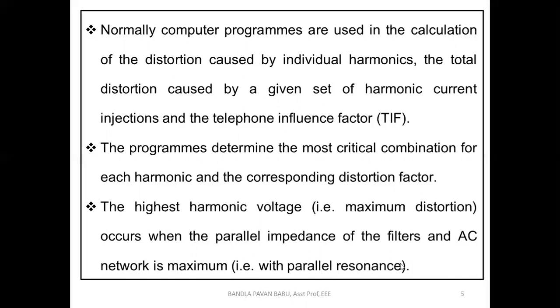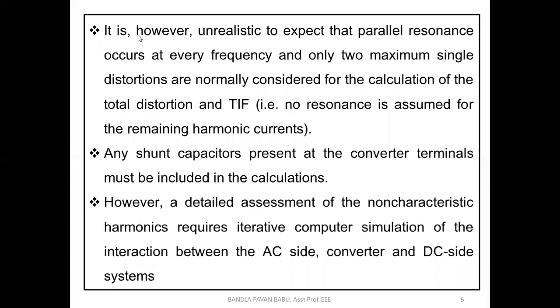This extreme case is expected when parallel resonance occurs. However, it is unrealistic to expect parallel resonance at every frequency — only two maximum single distortions are normally considered for calculating total distortion and TIF; no resonance is assumed for remaining currents. Practically, we cannot guarantee that harmonics will always reach a fixed maximum value, so we must consider additional worst-case values as well, similar to allowing margins beyond six times short circuit current.